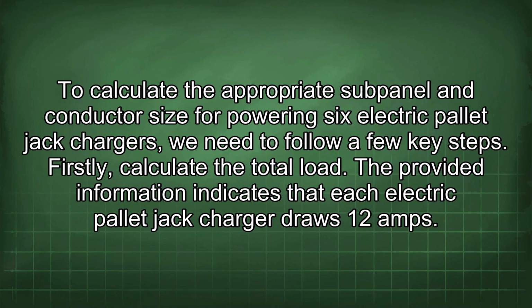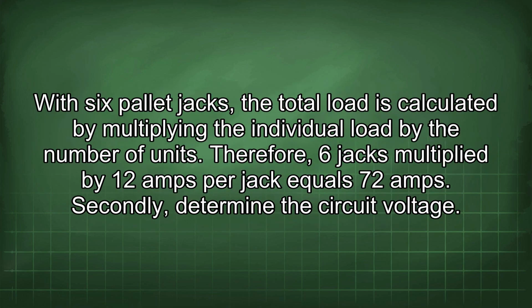To calculate the appropriate subpanel and conductor size for powering 6 electric pallet jack chargers, we need to follow a few key steps. Firstly, calculate the total load. The provided information indicates that each electric pallet jack charger draws 12 amps. With 6 pallet jacks, the total load is calculated by multiplying the individual load by the number of units. Therefore, 6 jacks multiplied by 12 amps per jack equals 72 amps.